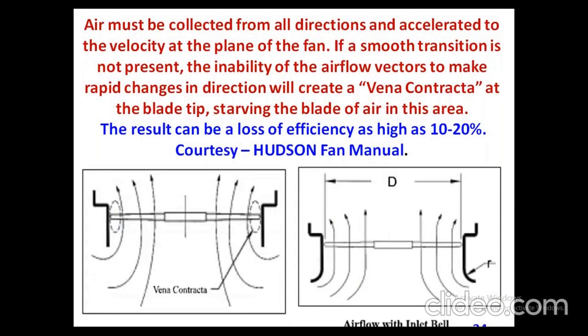This vena contracta is another point which we have come across in many textile mills, and we have done it for some textile mills in the north. You can see airflow with no inlet bell, and airflow with inlet bell. You can see the vena contracta point where there is a tip clearance. Instead of a 1250 mm dia, if you have fixed a 1200 mm fan with more than 50 mm clearance, this itself is a loss of 10 to 20% that is happening in each and every textile mill. We see to it that the tip clearance is maintained at less than 1%. If it is 1200, it should be maintained at less than 20 mm.